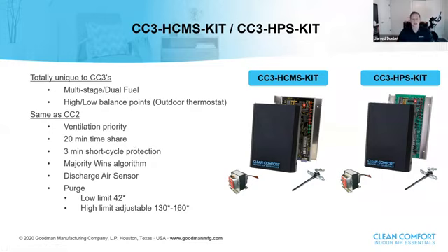And what that is, if you have a situation where a zone is calling for heating and then maybe another zone or two zones are calling for cooling, well, maybe the stat in that zone calling for heating is broken, or maybe one of the kids went and messed with it and turned it up as high as it could go. So the system's just not satisfying that zone. Well, after 20 minutes of attempting to satisfy that zone, our panel will drop the call, go over and satisfy the other calls that came in, and then come back to the call that's needing to be satisfied, which is great for apartment type or duplex type situations that are going to be zoned. So you never run into a situation where some zone is not going to get the air that it's calling for.